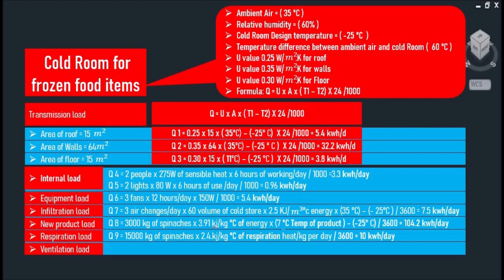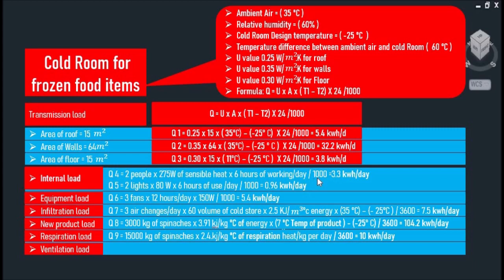The second thing, the internal load, which is the amount of total energy generated by people, lights, and equipment. People gave off heat according to the level of activity. As you can see, we have two people working, and each of them has a heat loss of 275 watts multiplied by hours of working per day divided by 1000. That comes to 3.3 kWh per day.